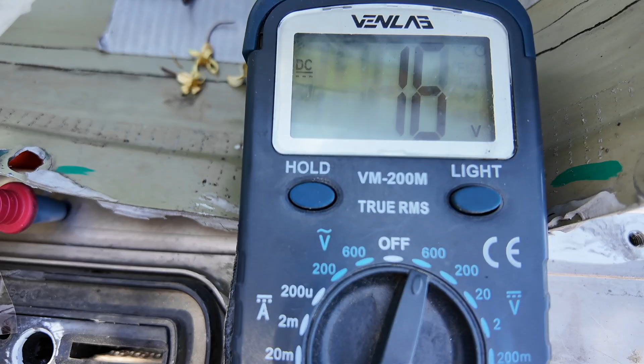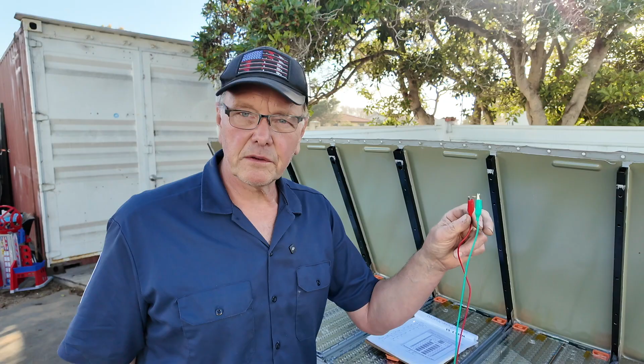Now with the pyro fuse out of the way, I want to test one more thing. I want to purposely install an insulation fault somewhere here in the battery, then use my chart to first calculate the voltages I should see on the contactors in the back. For that, I'm going to use a 100 kilo ohm resistor.